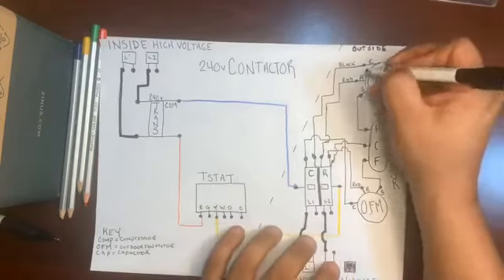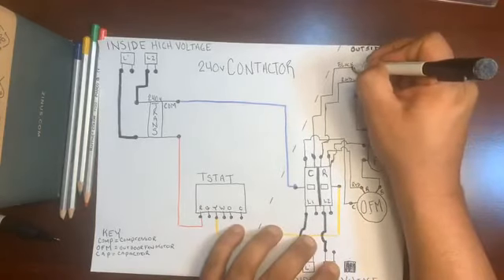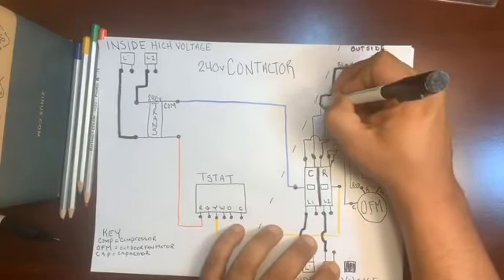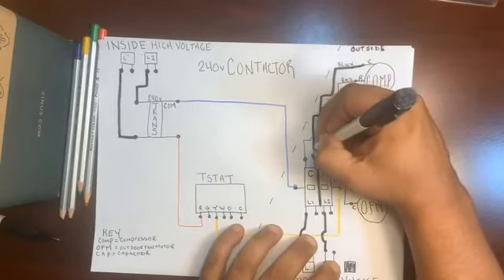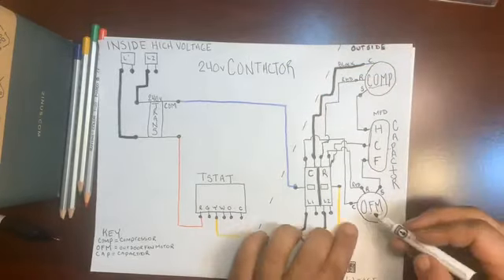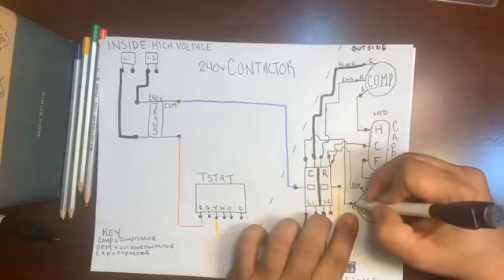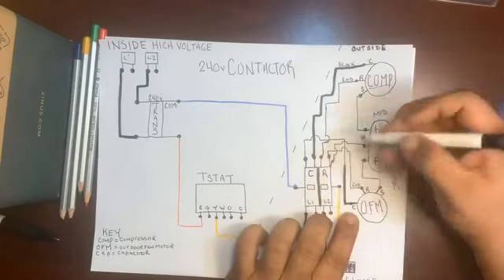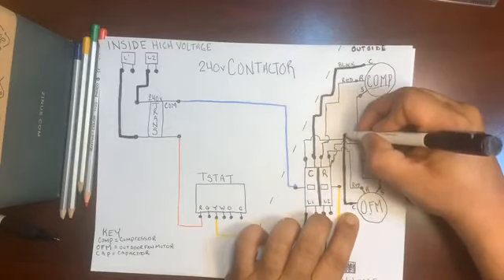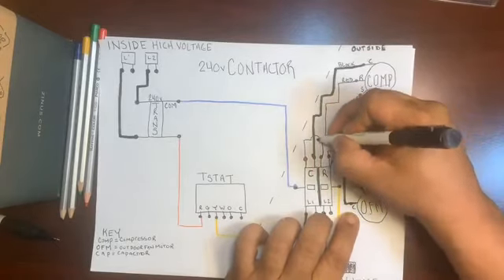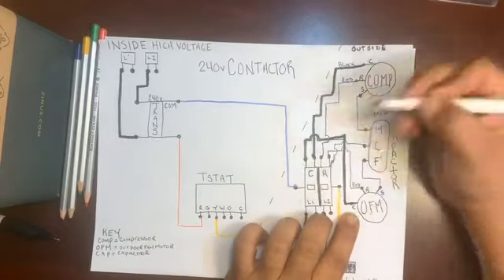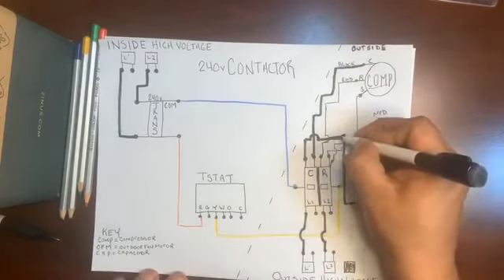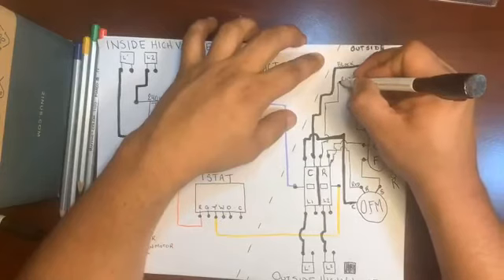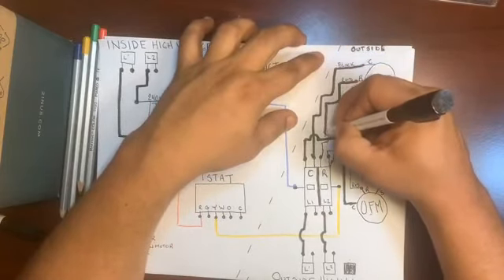It's going to get a little tight here, but we can do it. We're going back to the common side of the compressor, bringing that on down, underneath. Very good. We'll do it back the same way, common side of the outdoor fan motor. Bring it underneath. And we close and we show the high voltage. Bring our red for our run. Bring it down. Go over your same wires, your nice bridge. And we're there.